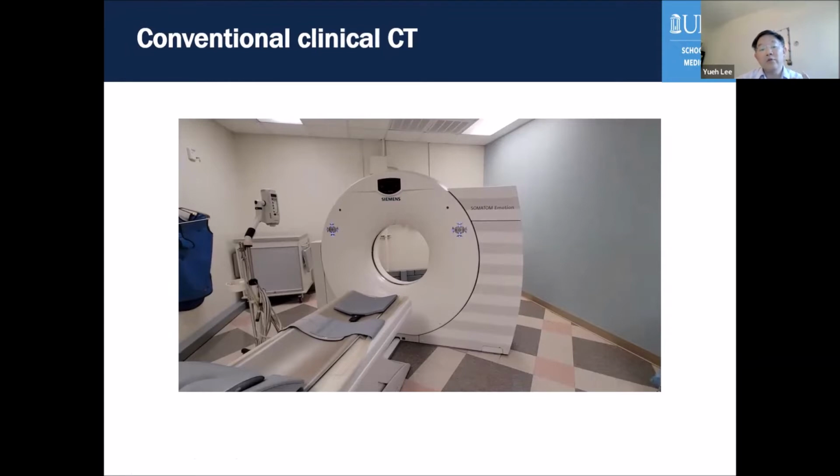And I want to give you a feeling for how large this thing is and how complex it can be, because you're rotating a gantry that literally weighs hundreds, if not 1,000 pounds, and you're rotating it quickly in this big circle. G forces do play a role, so it's very important. There's a limit to how fast we can run these things.